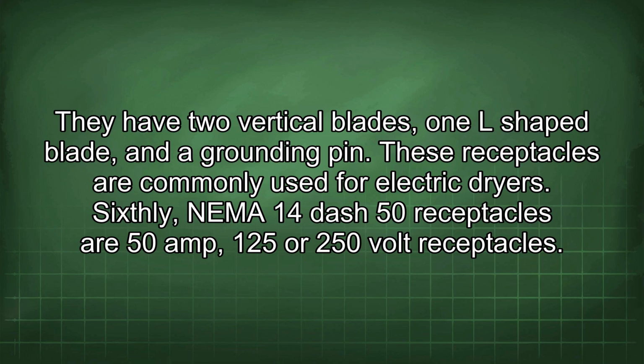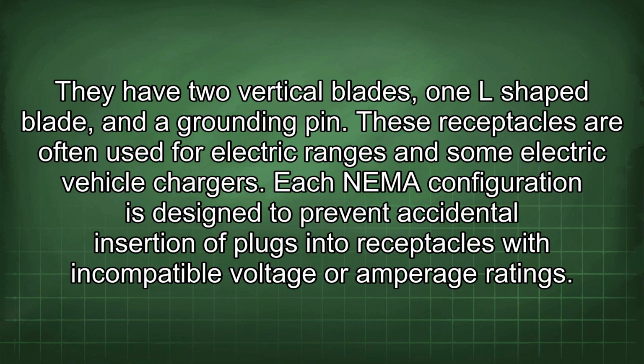Sixthly, NEMA 14-50 receptacles are 50 amp, 125 or 250 volt receptacles. They have two vertical blades, one L-shaped blade, and a grounding pin. These receptacles are often used for electric ranges and some electric vehicle chargers. Each NEMA configuration is designed to prevent accidental insertion of plugs into receptacles with incompatible voltage or amperage ratings.